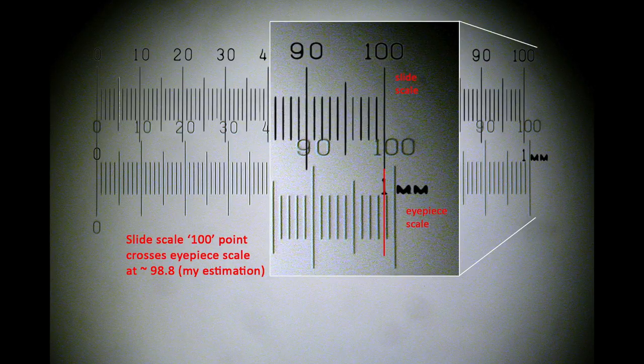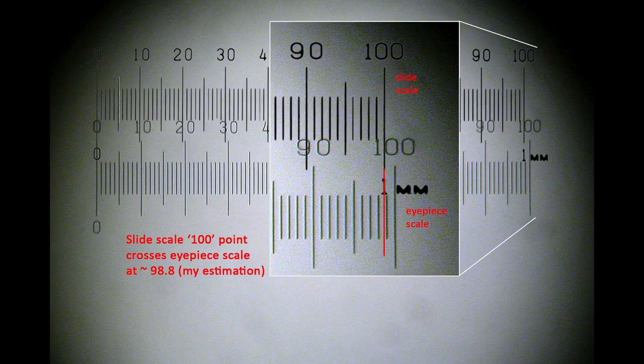When using the 10x objective, the two scales appear at first glance to be the same, therefore you could use the eyepiece scale without calibration, assuming it represented 1mm, and make measurements accordingly.